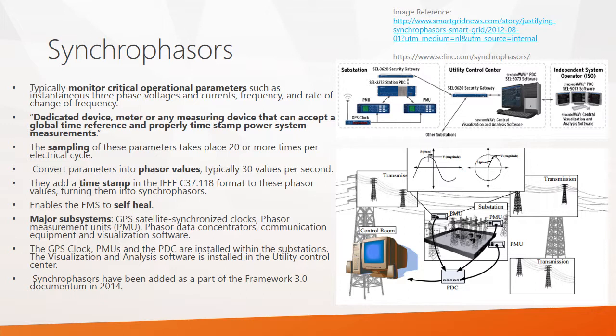The sampling of these parameters takes place about 20 or more times per electrical cycle. The conversion of parameters into phasor values takes place at about 30 values per second. They add a timestamp in a specified IEEE format to these phasor values, thereby turning them into synchrophasors.